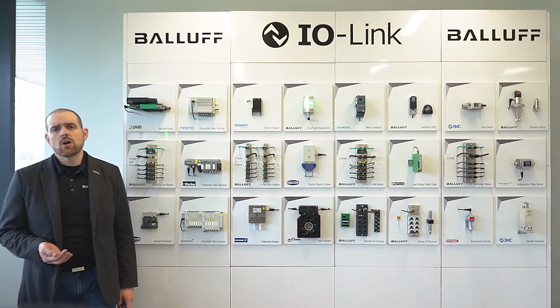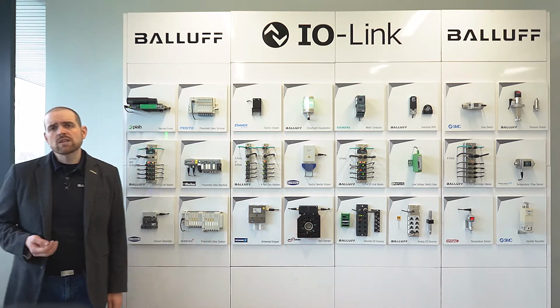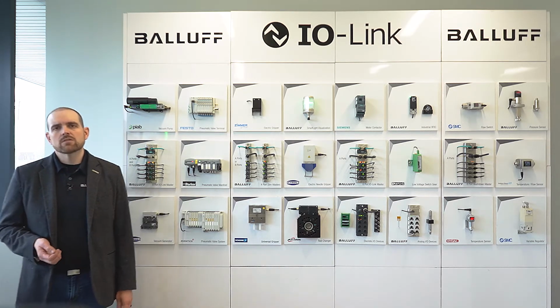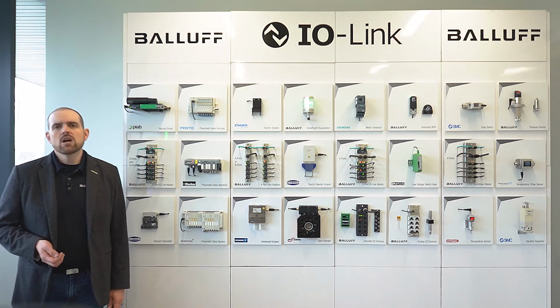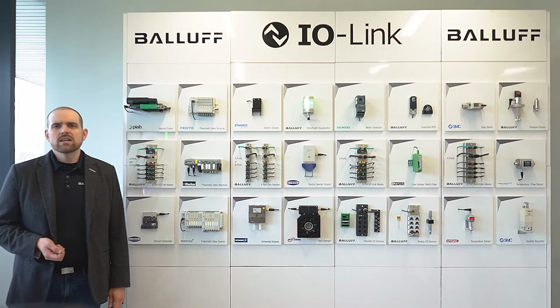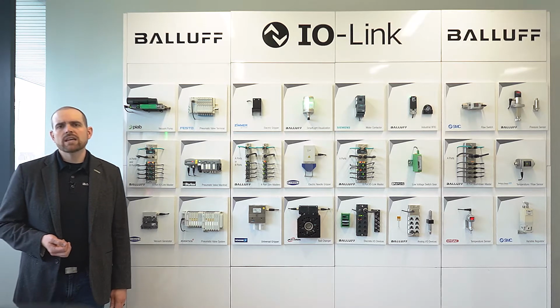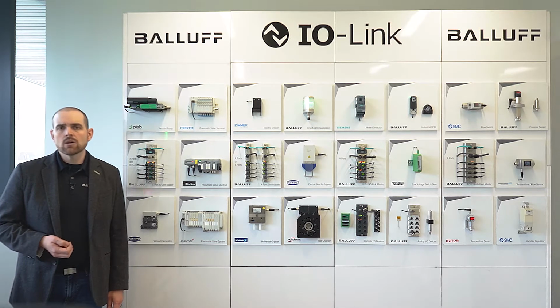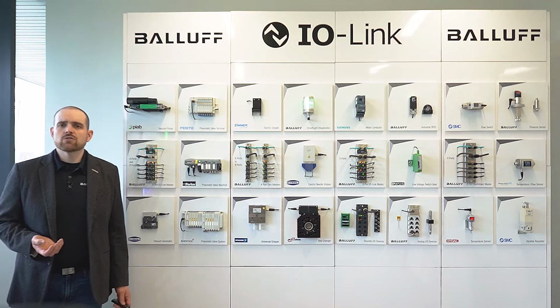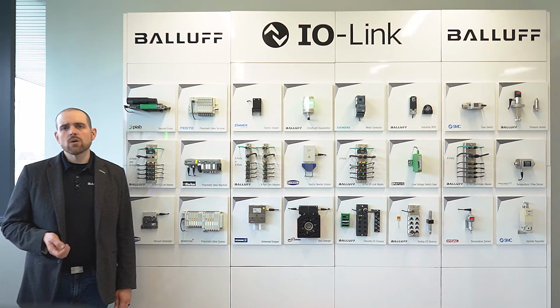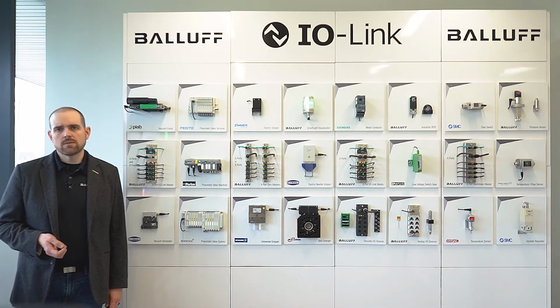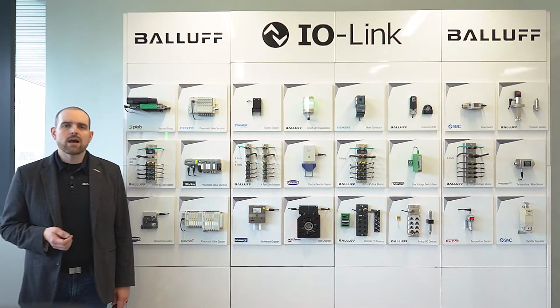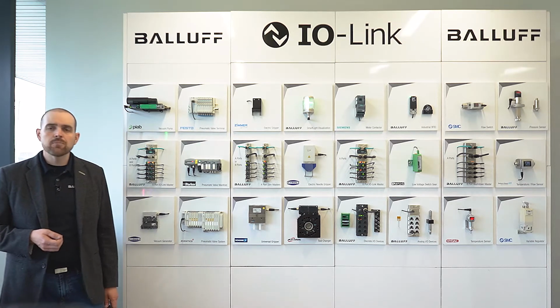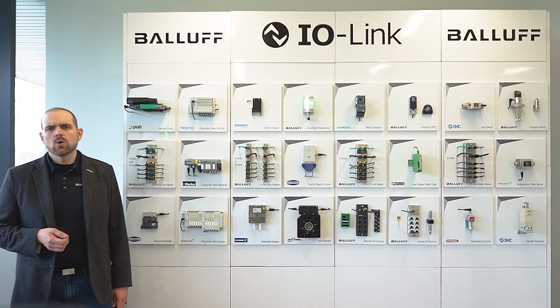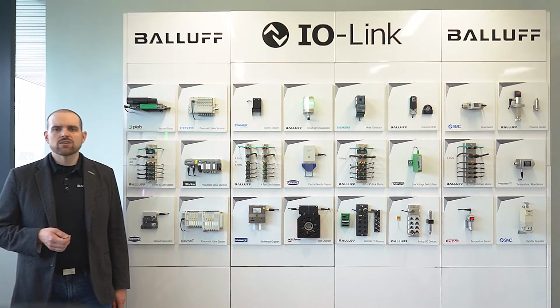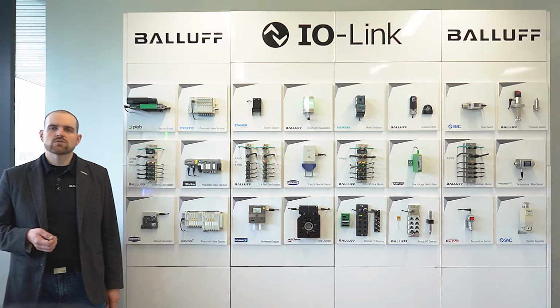The other thing to talk about is that with masters, there are two types of ports available in an IOLink master. The first type is called an A port, which uses 3 pins primarily: pin 1 is power, pin 3 is common just like a traditional sensor, and pin 4 is used for IOLink communication. So an A-style port is good for input devices like smart sensors or devices that are just monitoring information—you'll see A ports used for those types of devices.